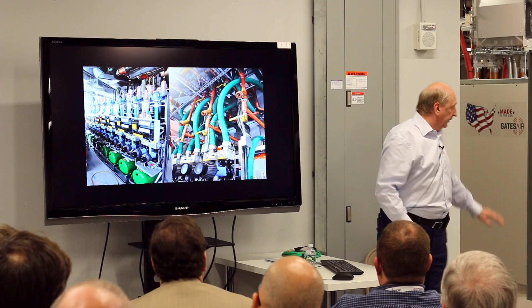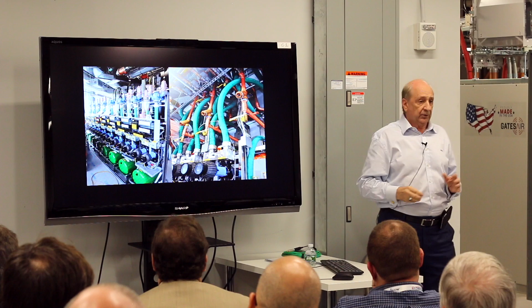Transmitters are all water cooled up here. We exhaust the heat through brazed plate heat exchangers here on the floor that go up to the 103rd floor where they hit another set of plate exchangers that go up to the cooling towers. So the primary loop is an open water loop that exhausts the heat into the air, goes to the 103rd floor, which is in a closed loop from 103 to here, and then we go to the heat exchangers with the broadcasters to then go from the plate exchangers to the transmitter and the pumps. The only area that is glycol is down here on the floor.